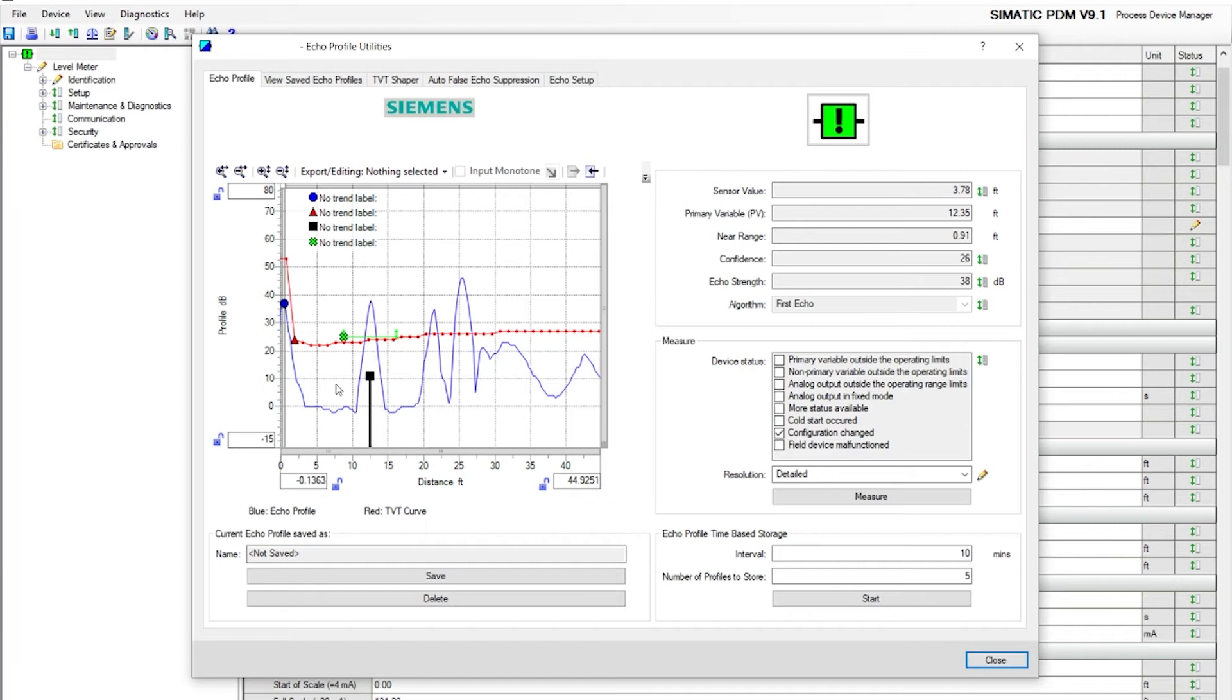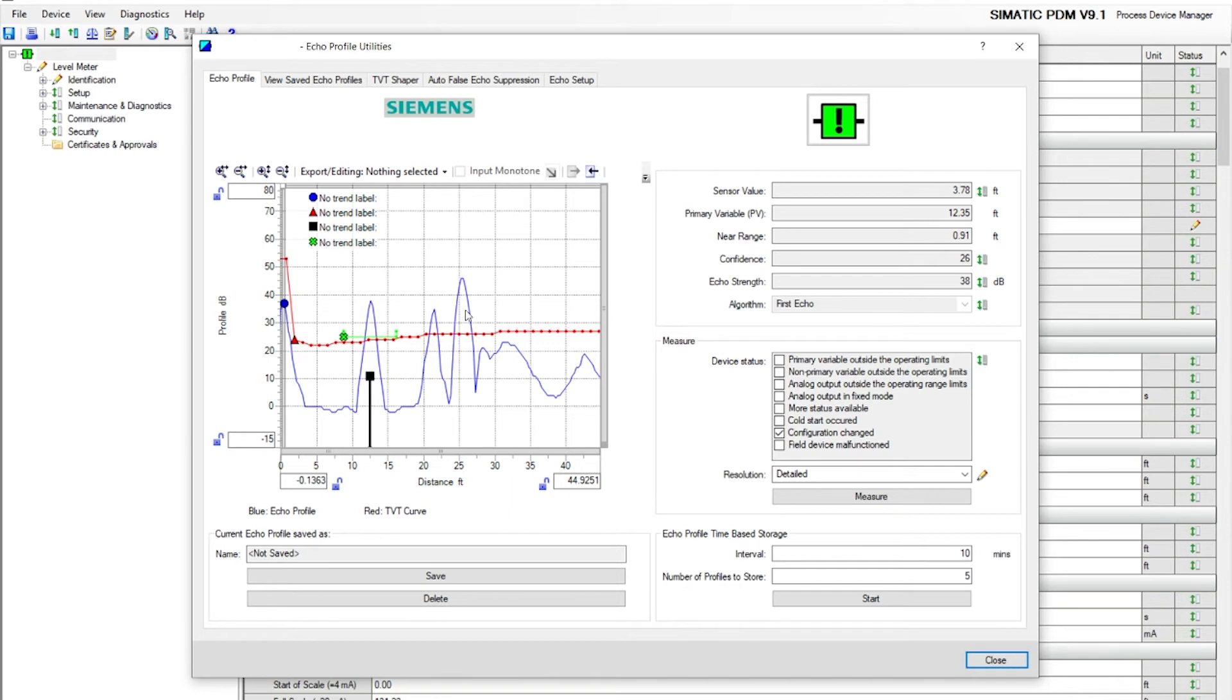As you can see, the black line is the echo marker, the actual echo that it thinks it's detecting or seeing. In this case, we're using this as a supporting beam. Second echo is a pipe. The third echo is the actual target for material.